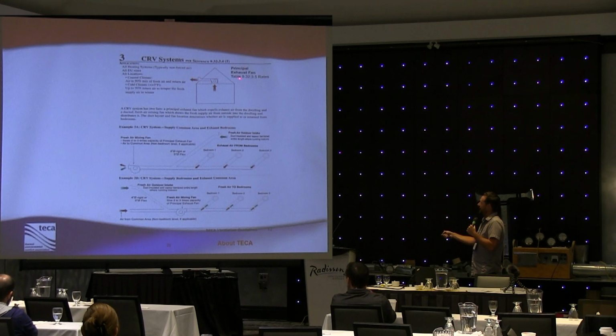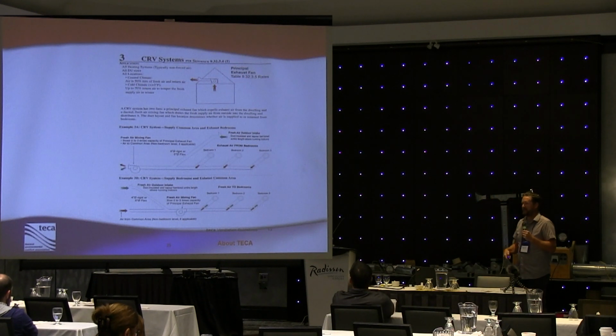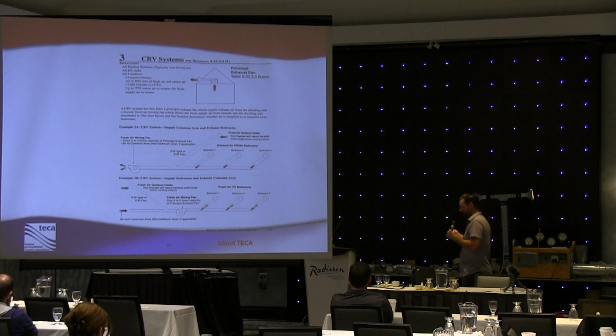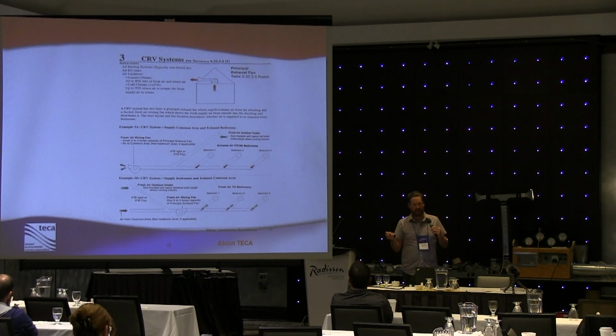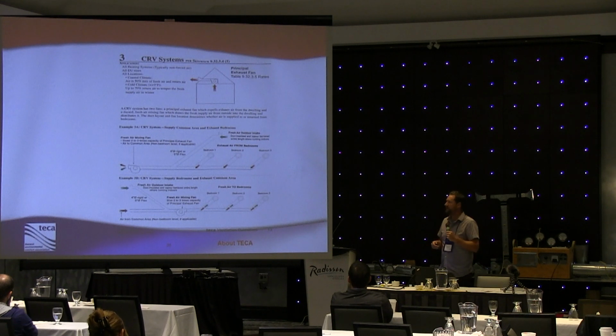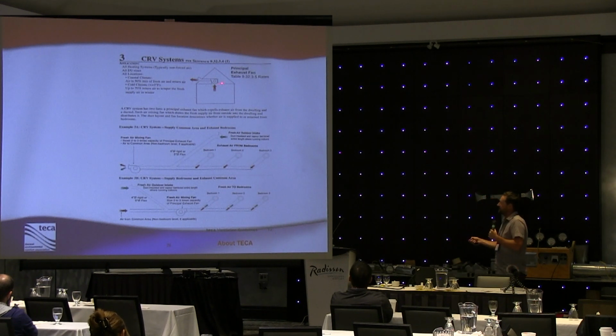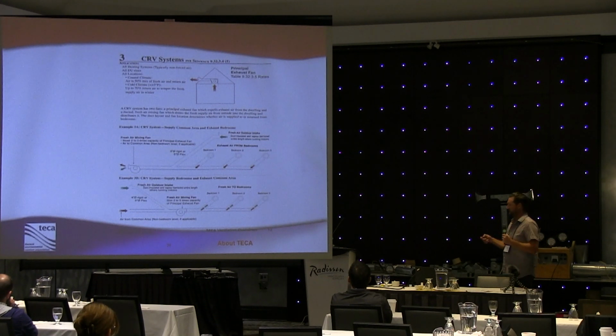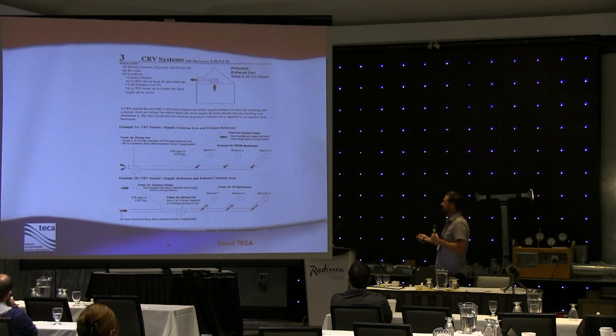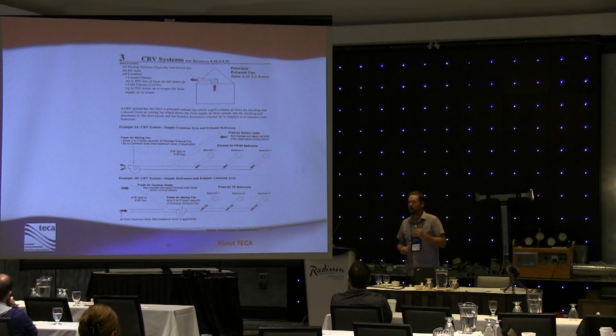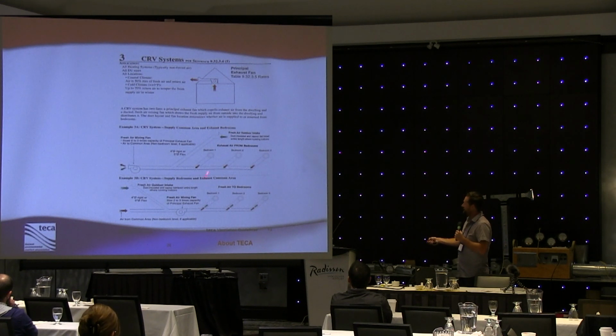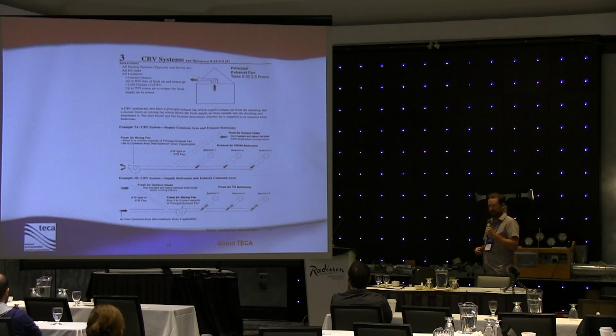So for example, if we were to look it up in the code tables in the BCBC, it would tell us, based on the size of the home, how many square feet it is, and the bedroom count, which gives us an idea of how many occupants are in the home. Based on those 2 criteria, it will give us a rate at which we must ventilate, whether it's 50, 100, 130 CFM. That's how many CFM we're going to have to exhaust at. So this fresh air mixing fan, if this was 100 CFM, this fresh air mixing fan on the coast would have to be 200 CFM.